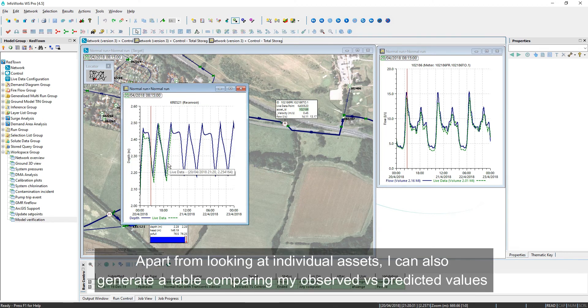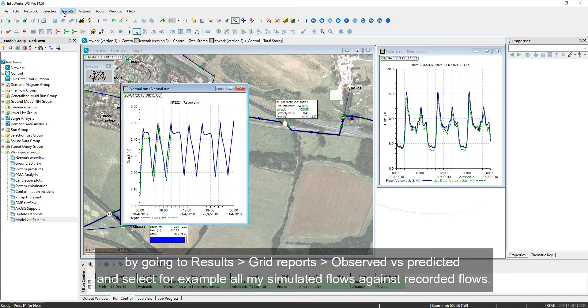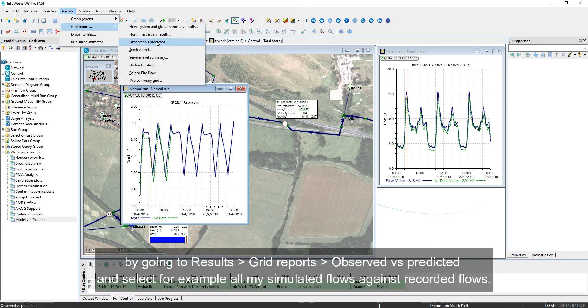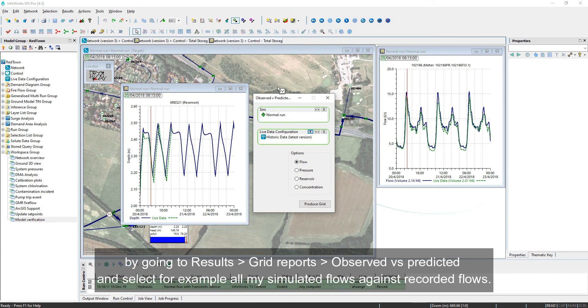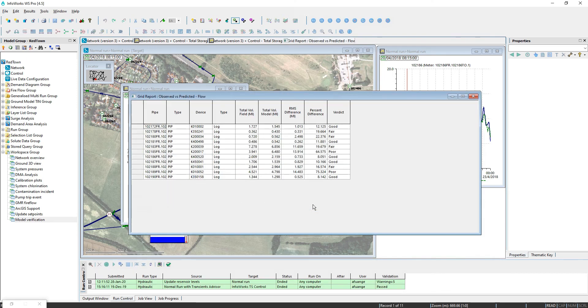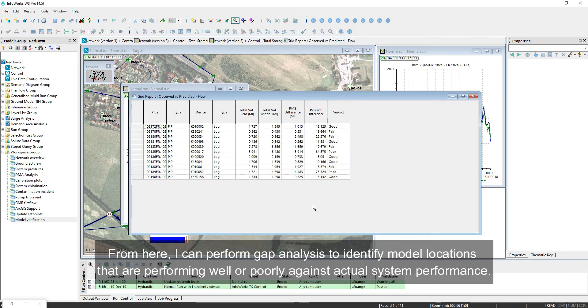Apart from looking at individual assets, I can also generate a table comparing my observed versus predicted values by going to Results, Grid Reports, Observed versus Predicted, and selecting, for example, all my simulated flows against recorded flows. From this summary table, I can perform gap analysis, wherein I can identify model locations or assets that are performing well or poorly against actual system performance.